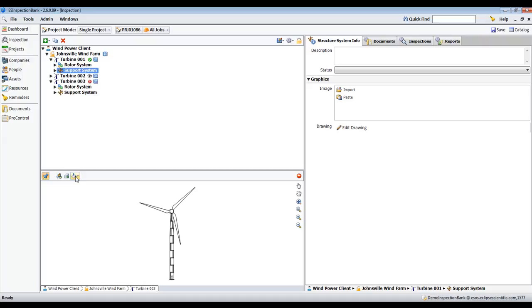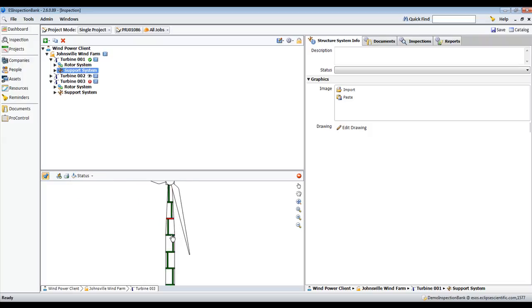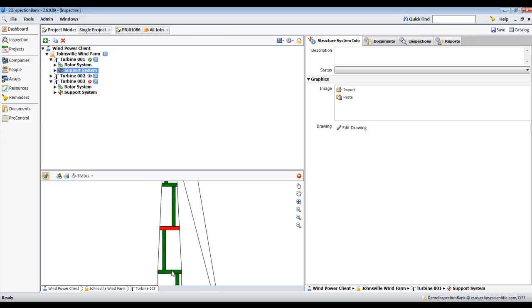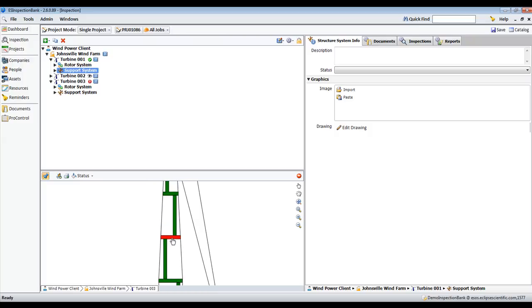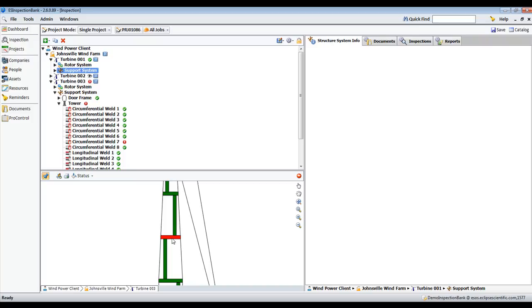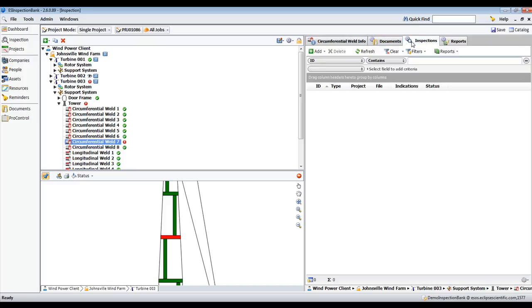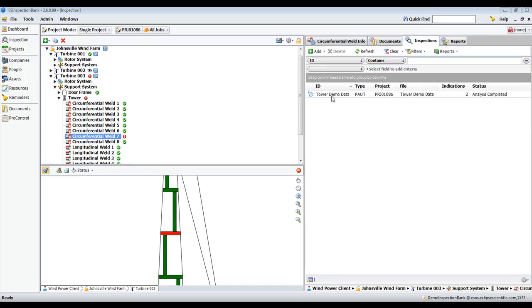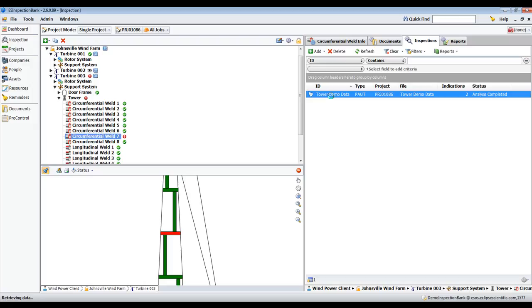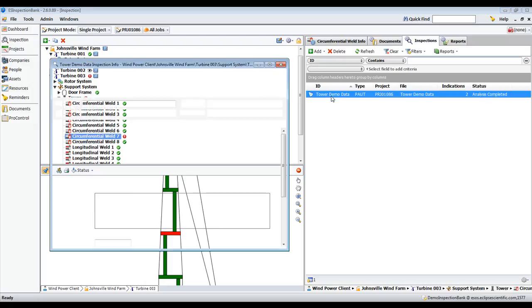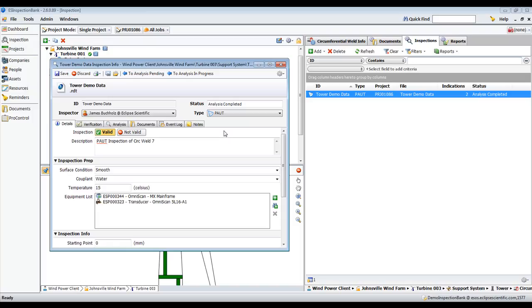By turning on the status option, the welds in the drawing will take on the status of the components they are linked to. Selecting the rejected weld will take me to that component, where I can check the details of the component and look at the inspections performed on it. I can tell this is a phased array inspection based on the icon, and opening it will give me access to the data file, as well as all the details from the analysis.